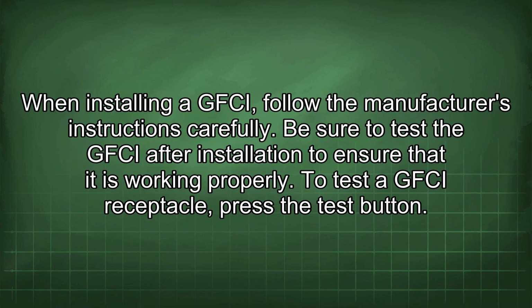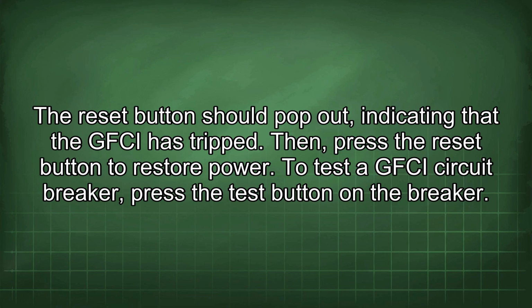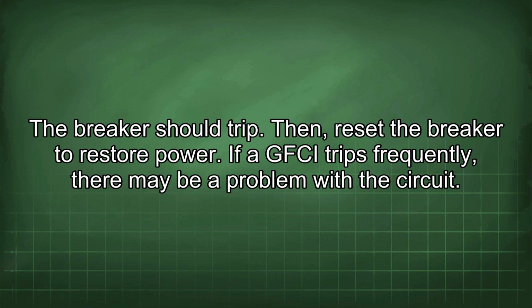When installing a GFCI, follow the manufacturer's instructions carefully. Be sure to test the GFCI after installation to ensure that it is working properly. To test a GFCI receptacle, press the test button. The reset button should pop out indicating that the GFCI has tripped. Then press the reset button to restore power. To test a GFCI circuit breaker, press the test button on the breaker. The breaker should trip. Then reset the breaker to restore power.